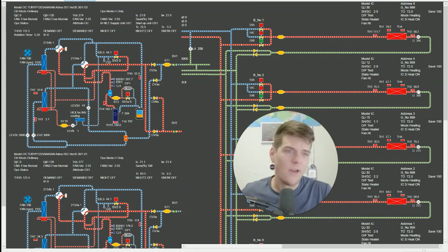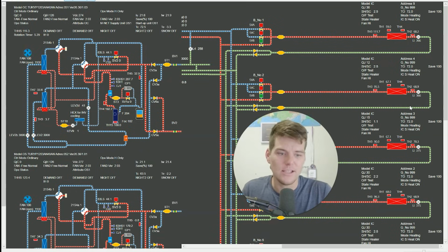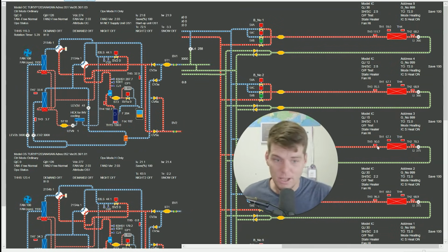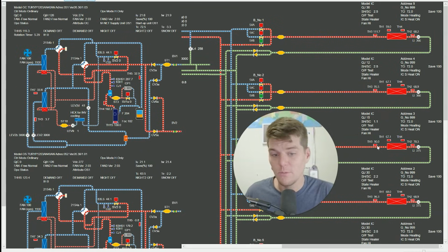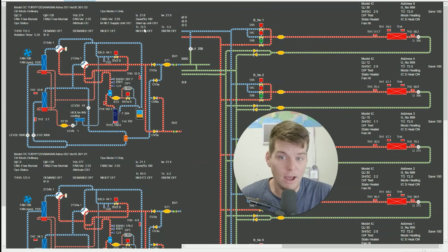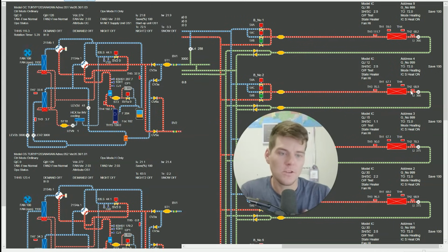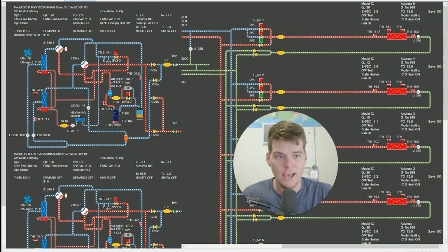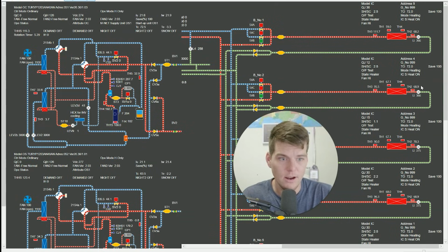Remember, the complaint was what? The complaint was a lack of heat, right? So if there is a lack of heat, then I would expect to see what? High delta temperatures across the indoor heat exchanger. Now, this isn't superheat, this is subcool. And if we look at what my TC is, remember 72, that's my measuring stick. So if that's the bottom of the threshold and I'm at 68 degrees, there's what, 4 degrees subcooling here.